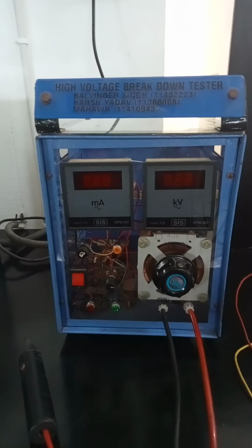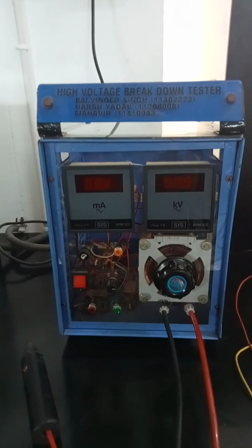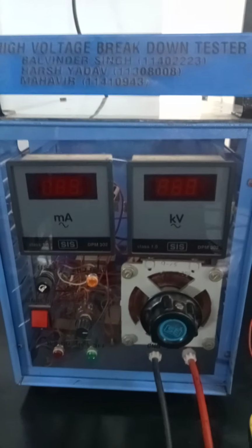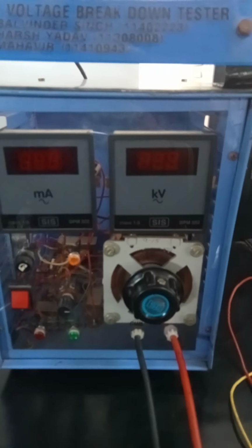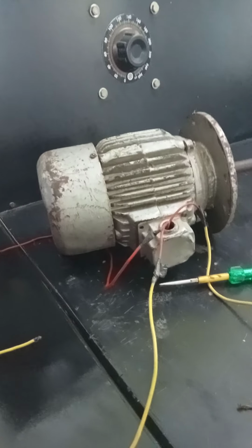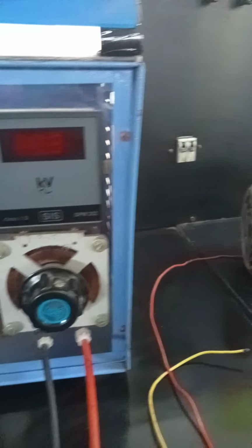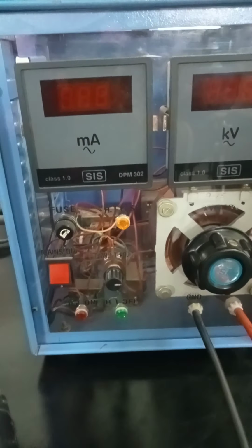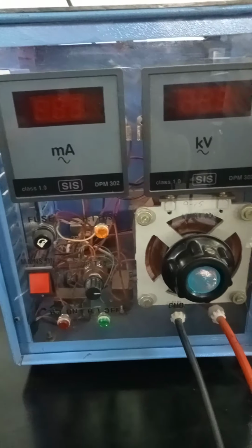So the next part of the experiment is, see, this is the equipment, high voltage breakdown testing. So this means that we have to apply high voltage. High voltage is around 1 kV across this 3-phase induction motor, and we will see whether the insulation is okay or not. So if there is an insulation failure, you will hear a beep sound from this machine, and if the beep sound does not come, that means the insulation of the motor is okay.